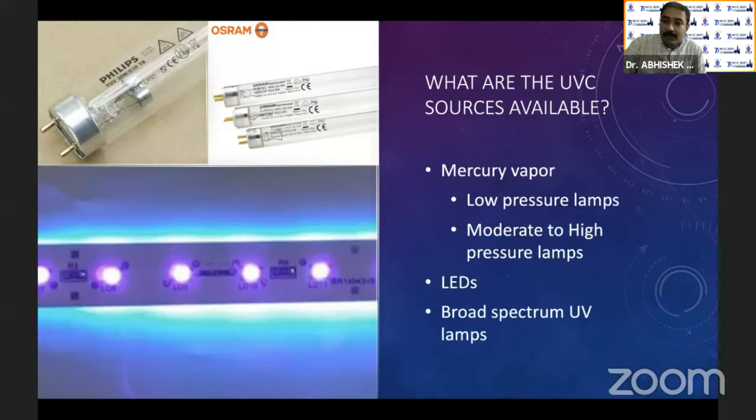There is another very important property of proper UV tube light glass: it allows only the germicidal UV to exit while trapping even shorter wavelengths. This is important because shorter wavelengths cause ozone formation inside the room, which is unhealthy — it can cause upper respiratory tract irritation and disease. That is why, if you've kept a room closed with UV light on for more than an hour, you should ventilate it for about 10 to 15 minutes before using it.